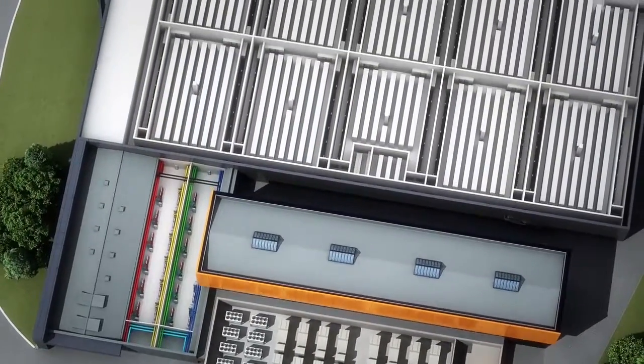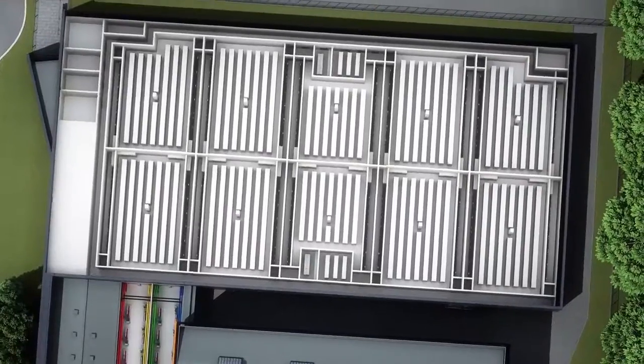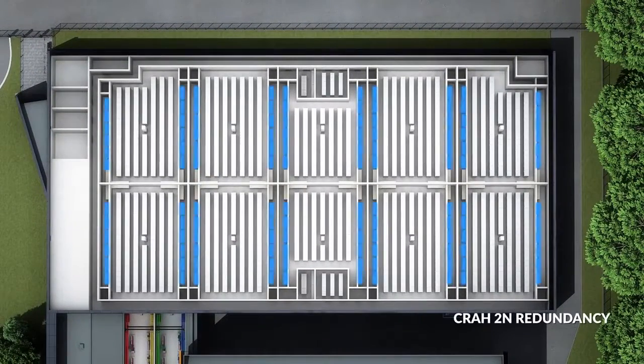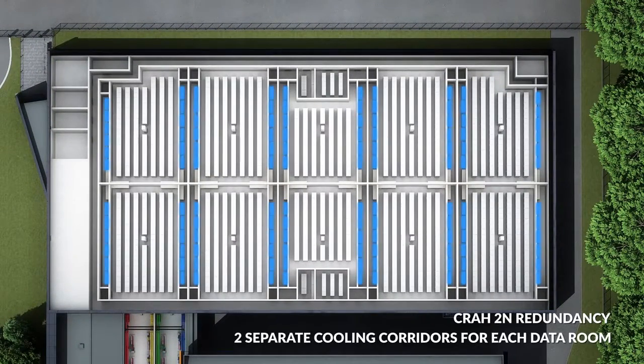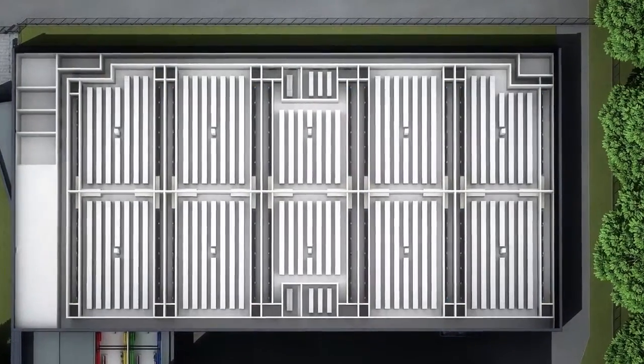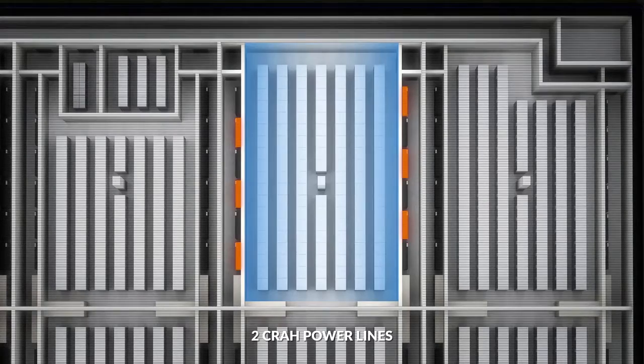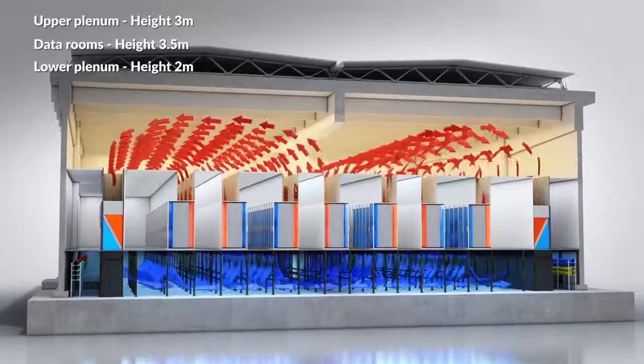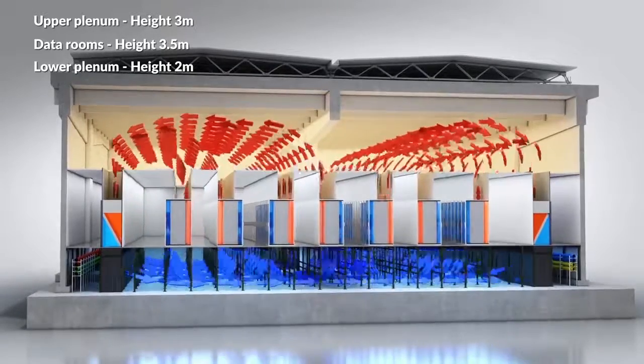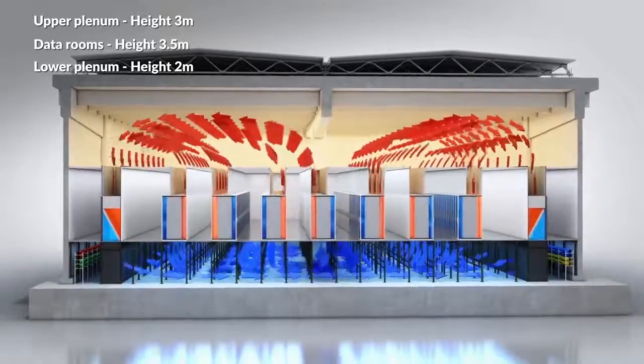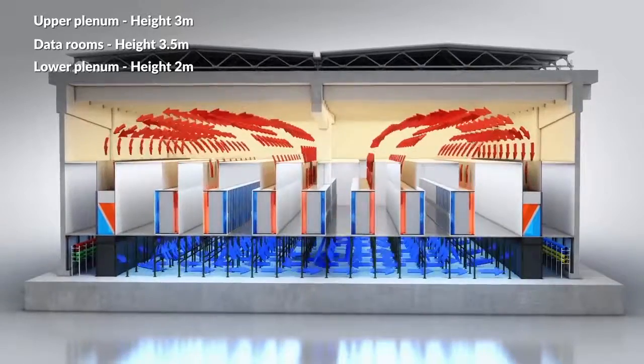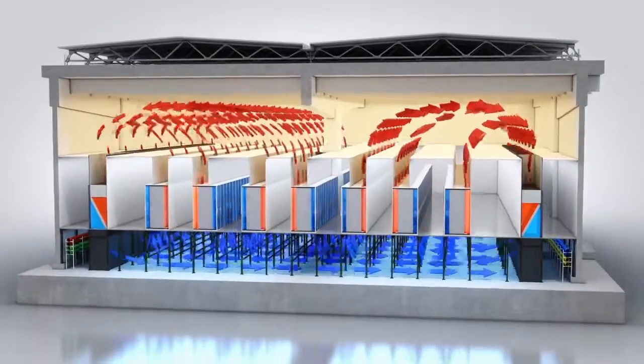Water-air thermal exchange takes place in the internal air conditioning units, which are completely redundant in the technical rooms, which are separate from each data room. The air conditioning units are supplied via 2 separate lines, ensuring that each one has the power needed to run the air conditioning system. The chilled air in the air conditioning units is first forced into the lower chamber, then channeled into the individual racks and finally drawn into the upper chamber.